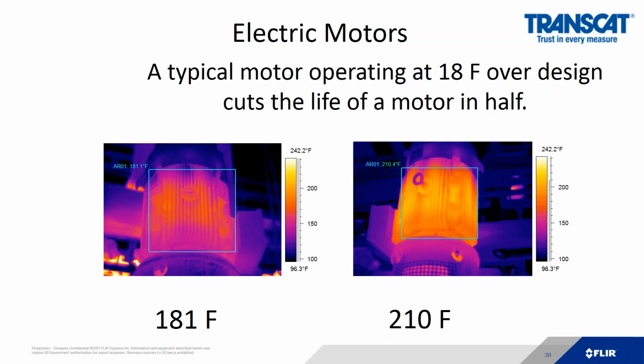Every motor has a faceplate on it, and the faceplate has an internal temperature rating. If we are 18 degrees above that internal temperature rating on the outside, you are going to cut the life cycle of that motor in half. So in this case, you are running this motor well beyond its thermal rating. Infrared's really good at motors that are hard to reach, hard to get, stuck in the air.